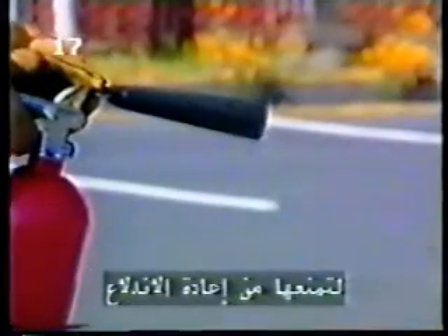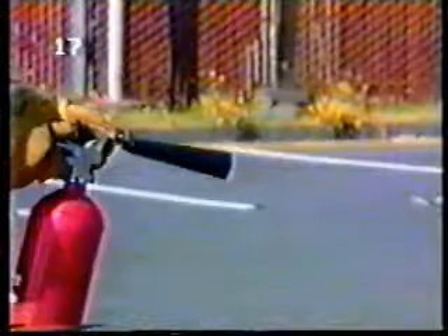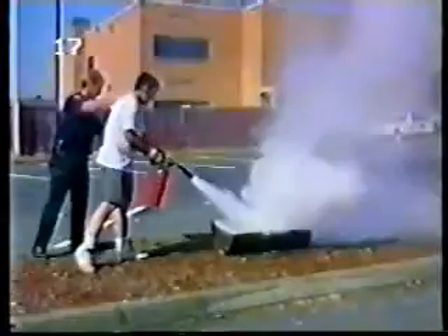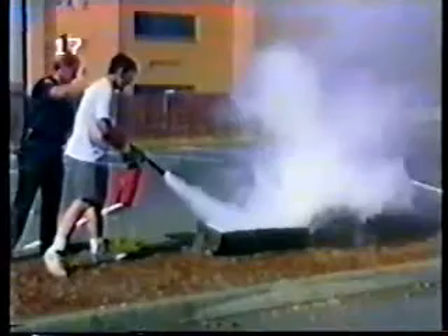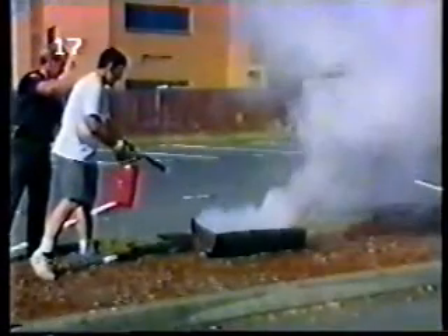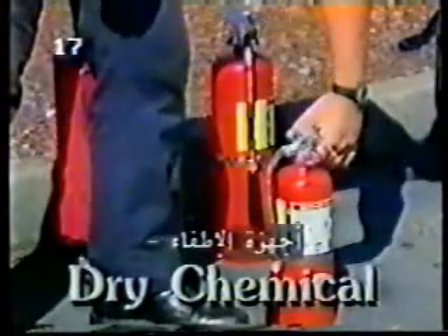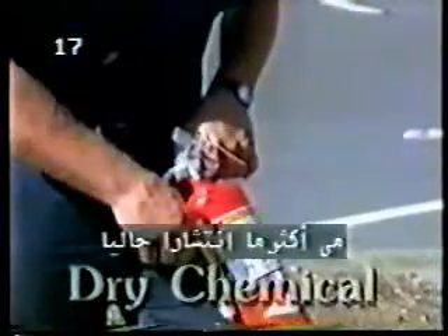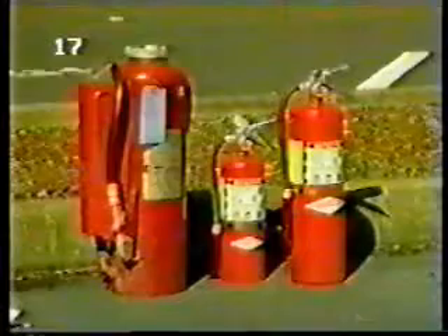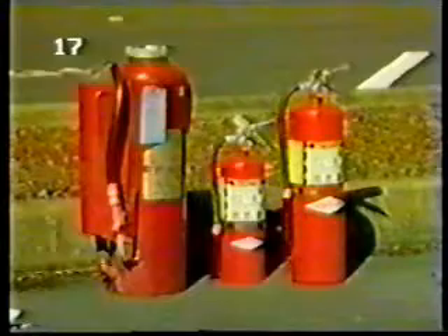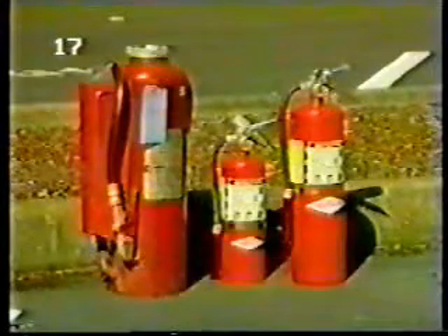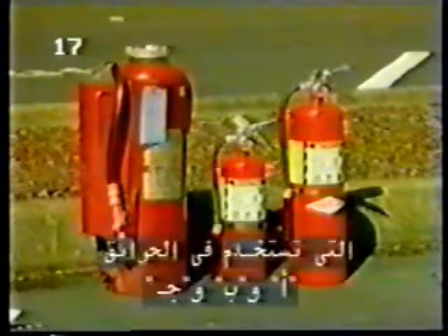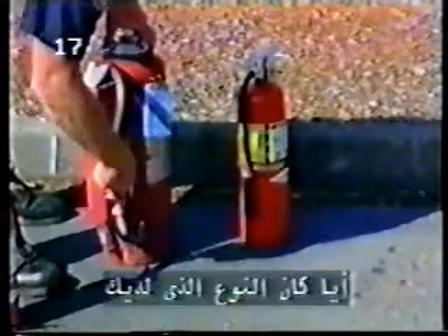As the name implies, the agent inside a dry chemical extinguisher is a chemical that comes out in a dry, powdery cloud. Dry chemical extinguishers are either a stored pressure type, which looks like a stored pressure water extinguisher, or a cartridge-operated type, which has a separate agent tank and pressure cylinder. To operate the stored pressure type, simply pull the pin and squeeze the shutoff handle, and the chemical will discharge.